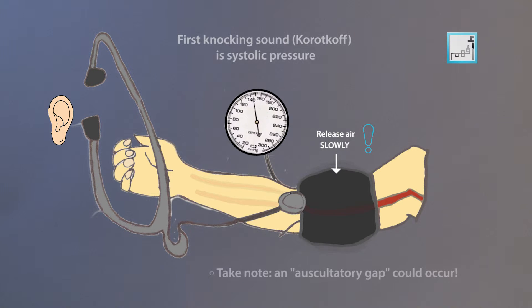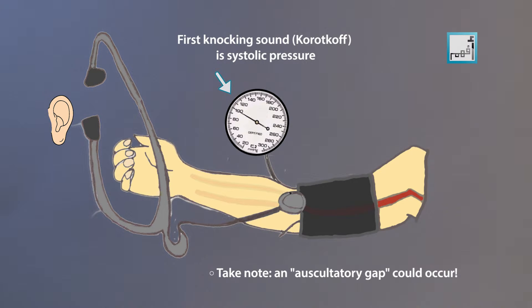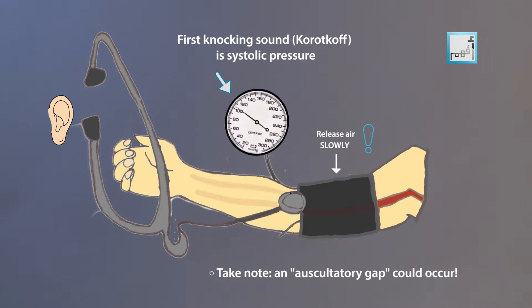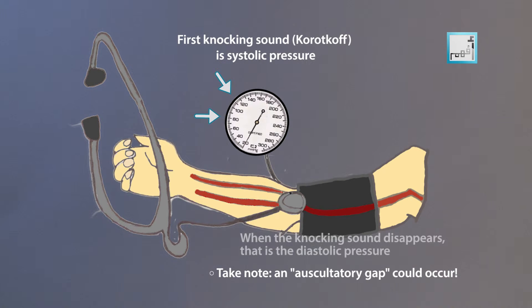As the pressure in the cuff falls, a whooshing or pounding sound is heard — it's called Korotkoff sounds — when the blood flow starts again in the artery. The pressure at which this sound begins is noted and recorded as the systolic blood pressure. The cuff pressure is further released until the sound can no longer be heard. This is recorded as the diastolic blood pressure. We can also palpate or feel the radial pulse to make sure that the lower reading is correct.